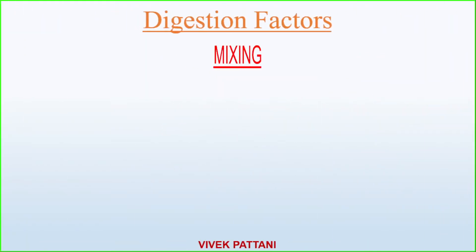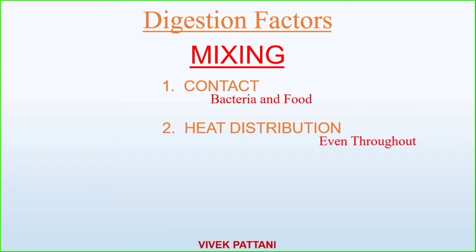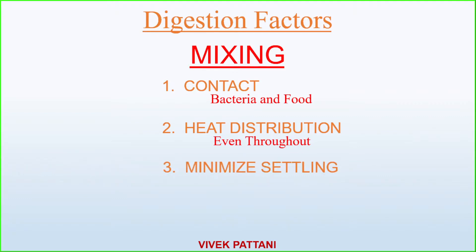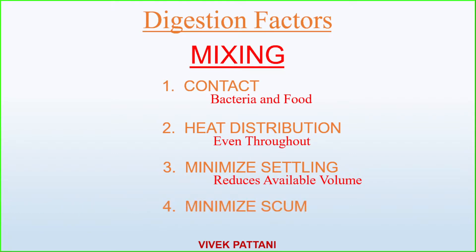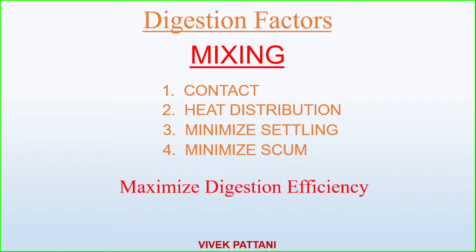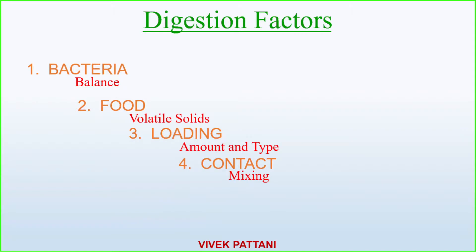Mixing should be done properly because it connects bacteria with food, distributes heat throughout the system, minimizes settling, reduces available volume loss, and minimizes scum. This reduces operational problems. Proper mixing leads to contact, heat distribution, minimized settling, and minimized scum, which together maximize digestion efficiency.